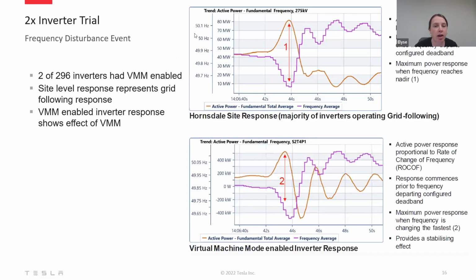So the next step in verifying virtual machine mode was the trial at Hornsdale. We enabled virtual machine mode in 2 of the 296 inverters. And the 2 graphs on the right show the difference between the plain grid following response and the machine mode enabled response. The one on the top is the whole site response. Given the portion of inverters with virtual machine mode on was so low, this is pretty much representative of a current source response. So you can see that the peak in active power, which is the orange line, corresponded to the maximum frequency deviation in the purple line.